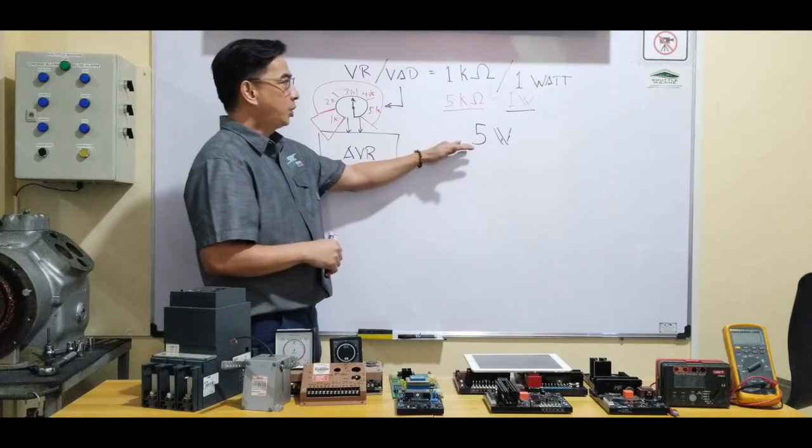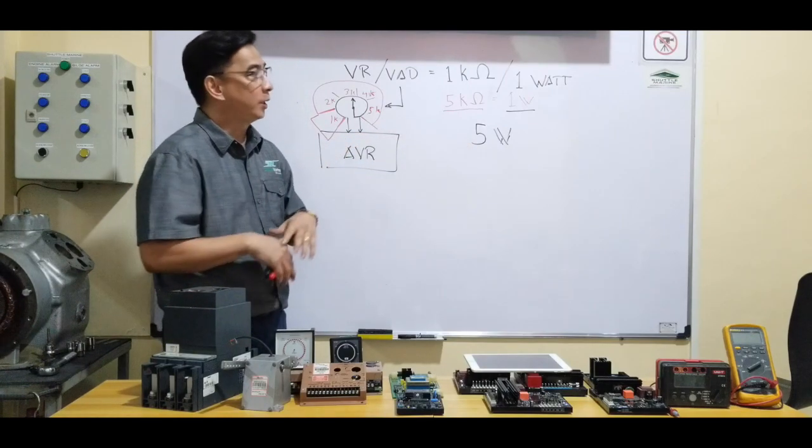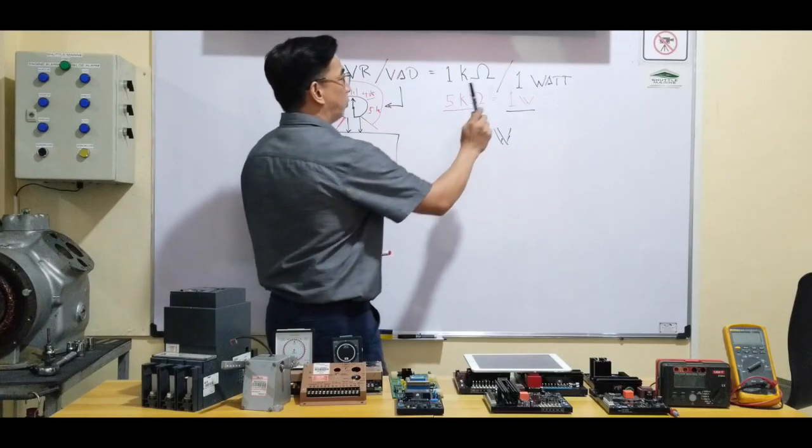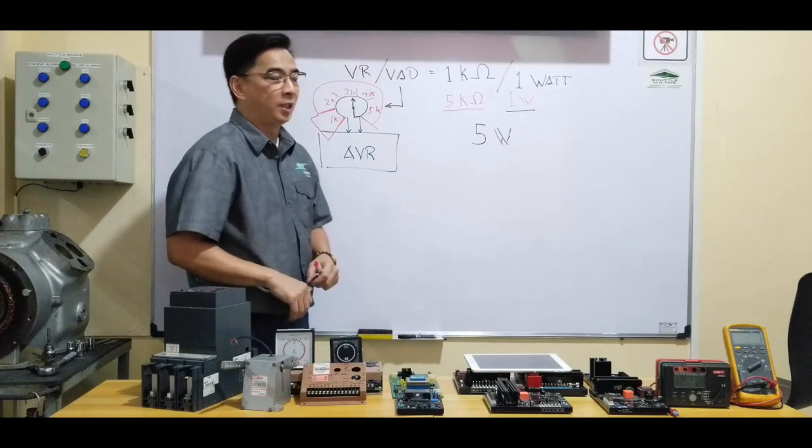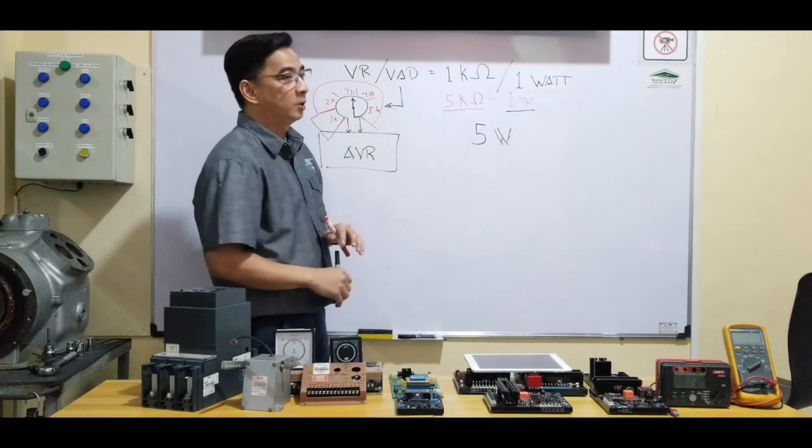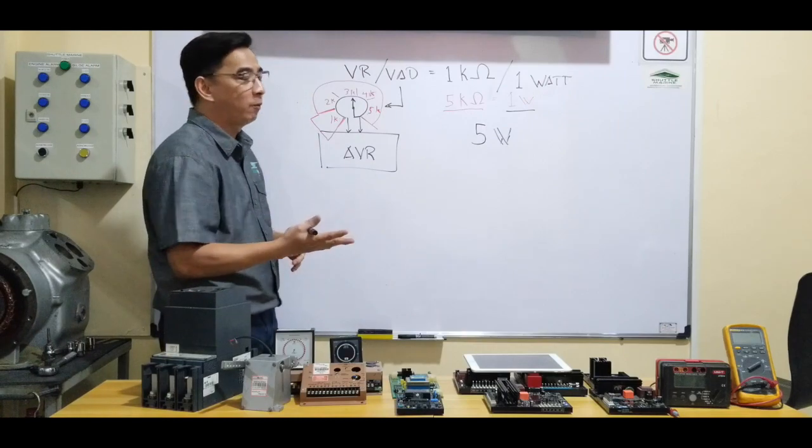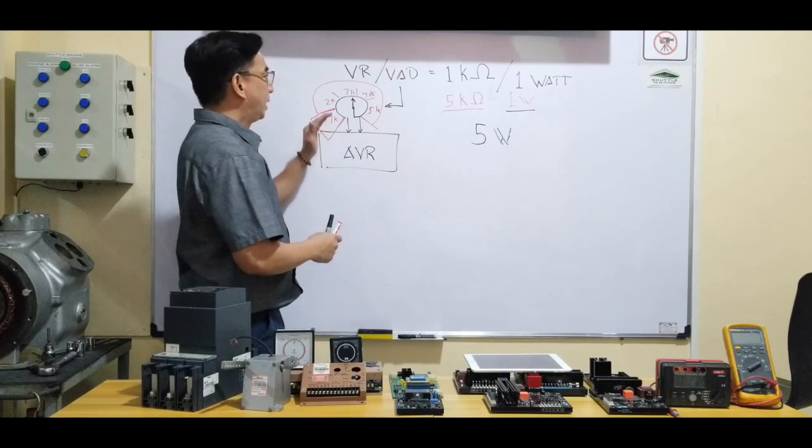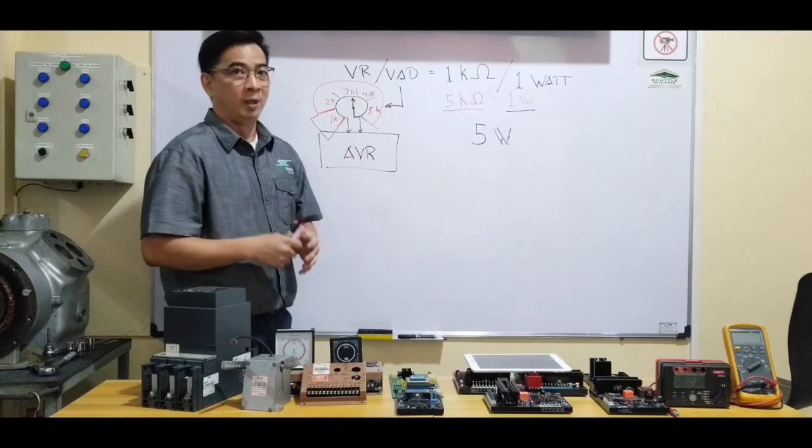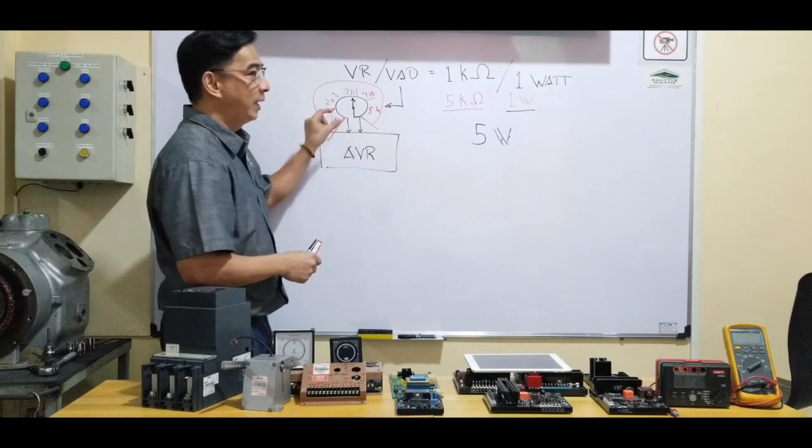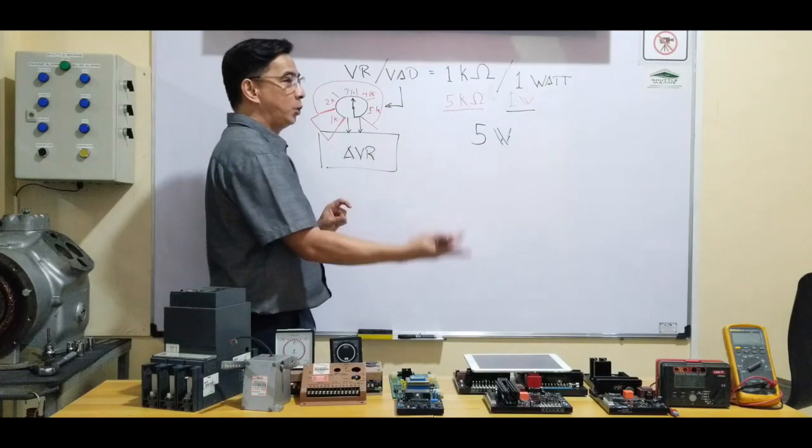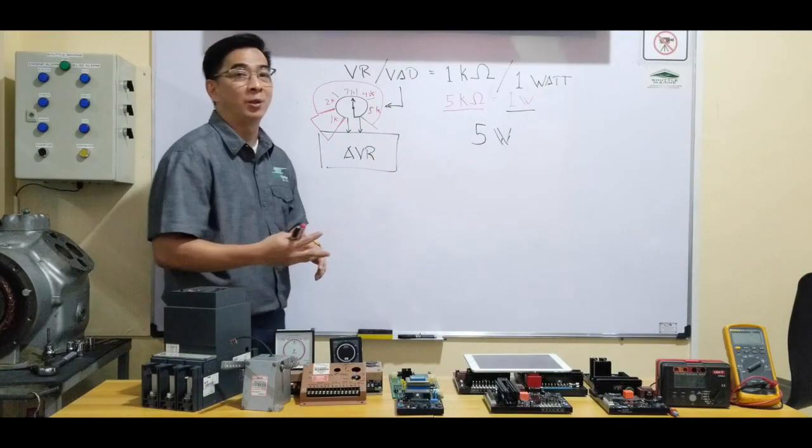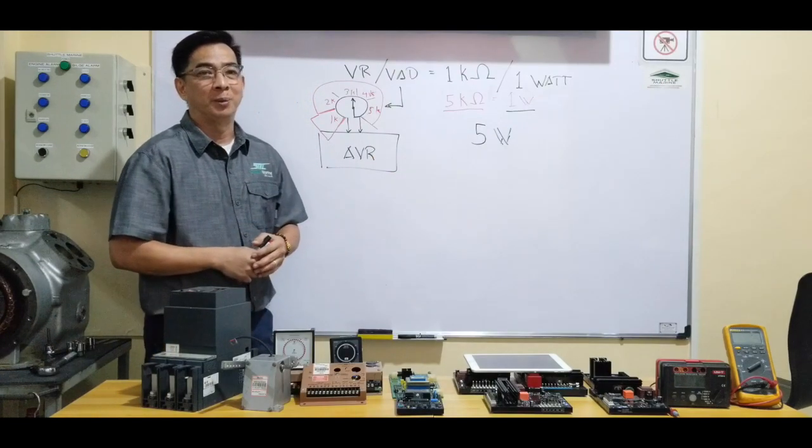Higher wattage creates higher current in the circuit. So it should be specific that we use the correct wattage. But on the resistance value, yes, we can use the higher value. But the thing is, it's quite difficult to adjust because it will have a very small variation and a huge effect on the voltage movement on our alternator output. Alright?